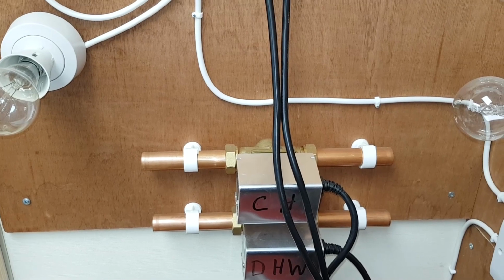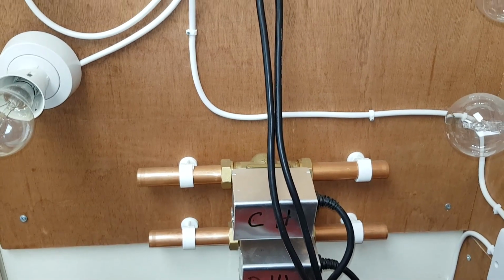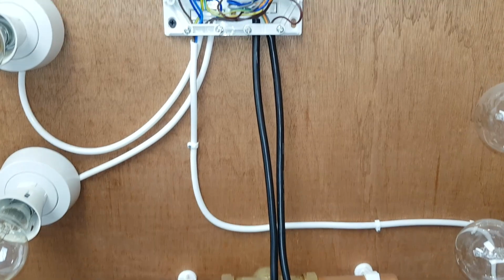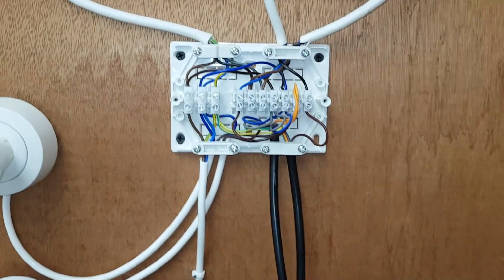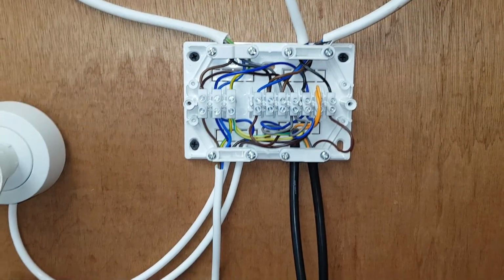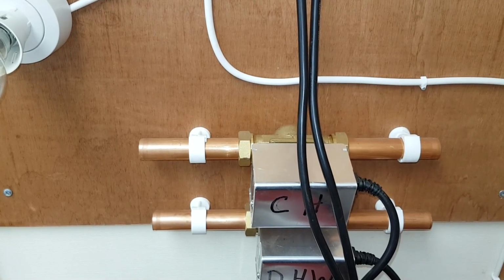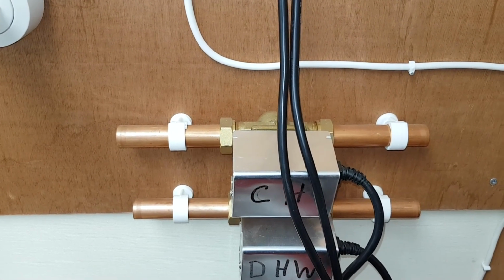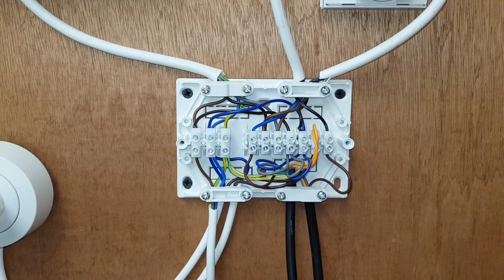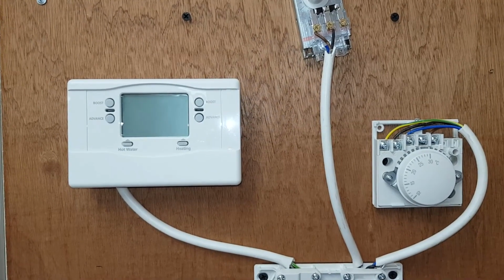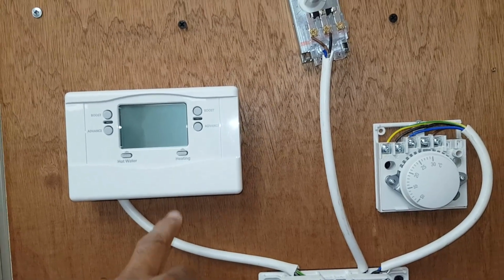Also, the micro switch could actually fail, meaning that the pump and boiler wouldn't be starting. That's it. Yeah, so there's two things that could fail. We've got the motor could fail, and we've also got the micro switch, as you said, could fail. Excellent. Well done. So, Miles, from terminal 3 from the programmer, what happens?